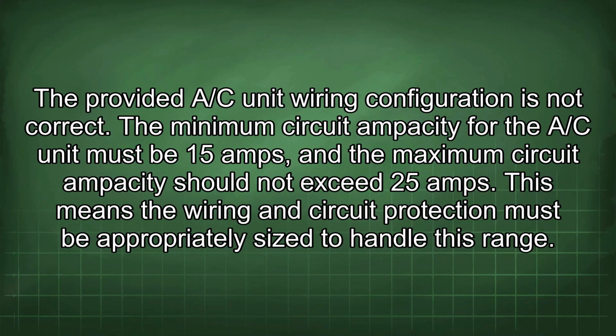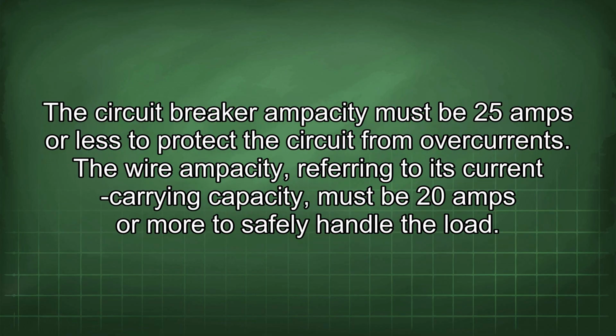Provided A/C unit wiring configuration is not correct. The minimum circuit ampacity for the A/C unit must be 15 amps, and the maximum circuit ampacity should not exceed 25 amps. This means the wiring and circuit protection must be appropriately sized to handle this range. The circuit breaker ampacity must be 25 amps or less to protect the circuit from overcurrents. The wire ampacity, referring to its current carrying capacity, must be 20 amps or more to safely handle the load.